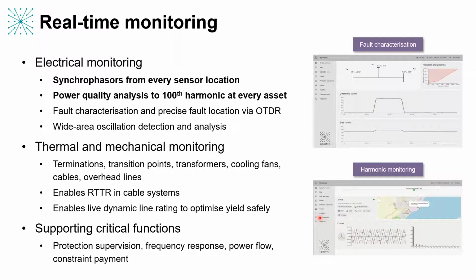As you said, Saul, there is a correlation for sure between low power quality and long-term damage to cables, because harmonics both hide energy that's being dissipated, usually by heat, in that system, and also particular harmonics are known to cause particular issues. And it's often not feasible to eliminate these issues prior to building a network of, for example, distributed generation. It's only once these networks have been built that these problems come to the fore. So we deploy systems that can measure the temperature, the current, the power quality, and also deal with the faults and fault location for underground, subsea and offshore systems.